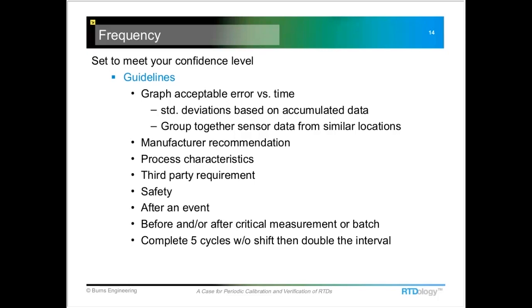One of the other things you can do to get a better idea of how the probes are performing in your process is to graph these errors over time, and maybe group together sensor data from various points within the plant that are very similar. It might be a steam line, it might be cooling water, those kinds of things, where you can group them together and get a bigger data set to help predict what a good calibration frequency would be.